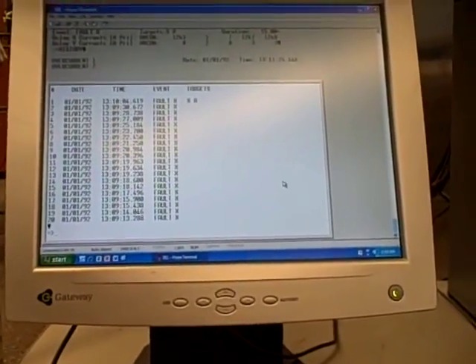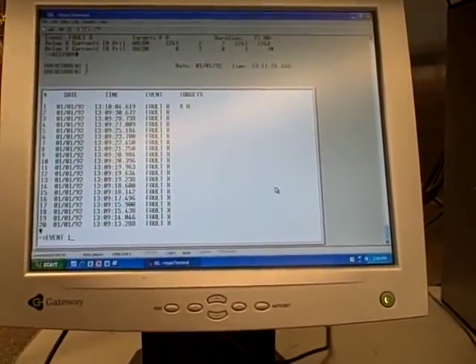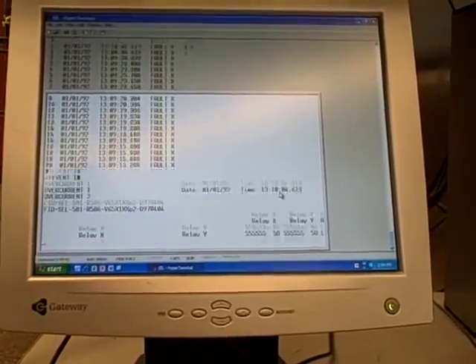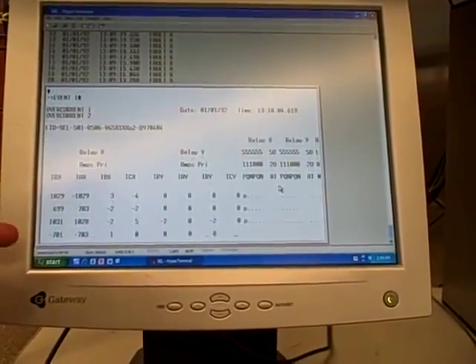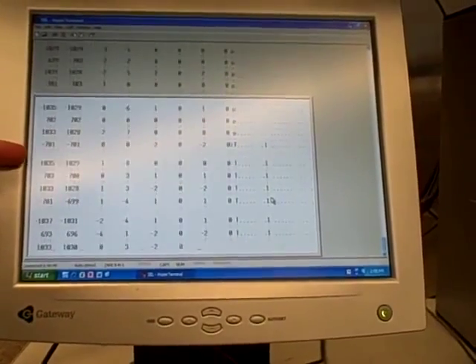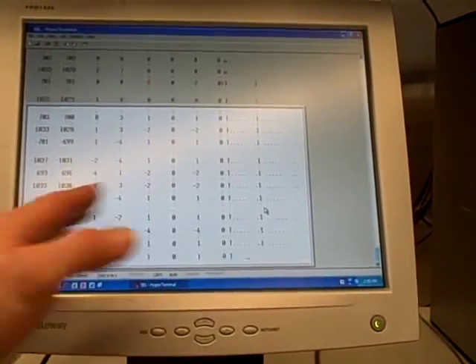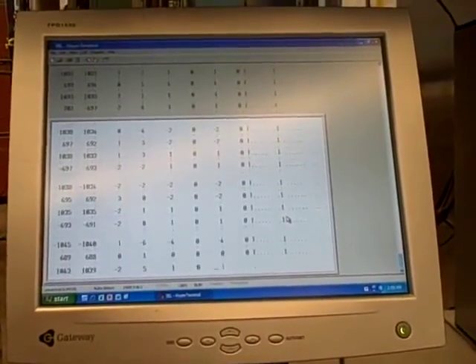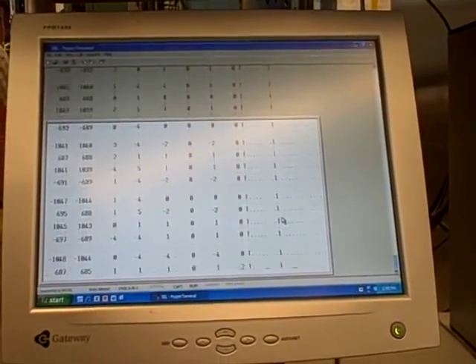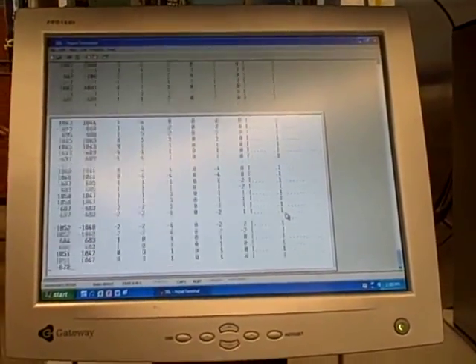I can get even more detailed event data. If I say event 1, I can take a look at the actual event step by step in time. This is showing me instantaneous values of the sine waves, phase A, B, and C, here as it goes along in a list. So if you wanted to interpret blow by blow what happened to the current at 15 cycles prior to the breaker's tripping, you get a record of it here.